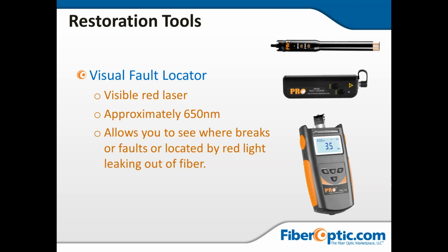Another thing you can do is look at whether a fiber connector interface is dirty. If you put a VFL on one side and don't look into it, but look sideways at about a 90-degree angle, and you see a little starburst at the top of a connector, then even without a video inspection scope you can tell there's contamination there. If you wipe it off and that starburst goes away, and looking from a 90-degree angle you don't see any glowing at the end of it, then you know you've got a clean connector.